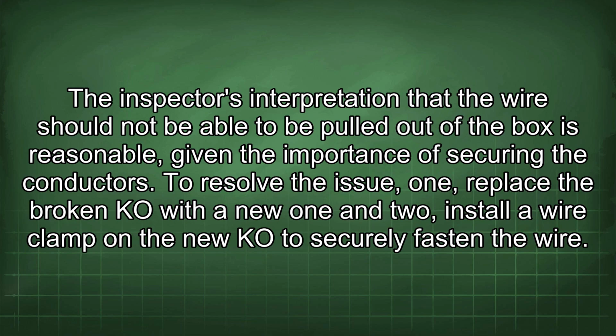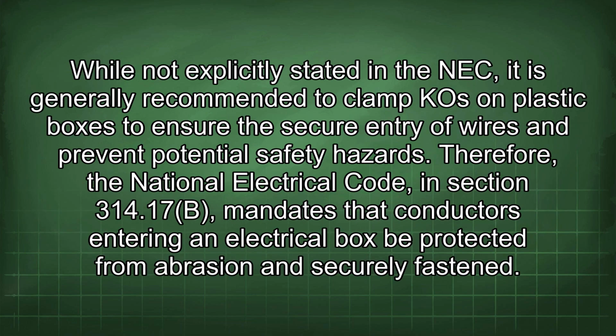To resolve the issue, one, replace the broken KO with a new one, and two, install a wire clamp on the new KO to securely fasten the wire. While not explicitly stated in the NEC, it is generally recommended to clamp KOs on plastic boxes to ensure the secure entry of wires and prevent potential safety hazards.